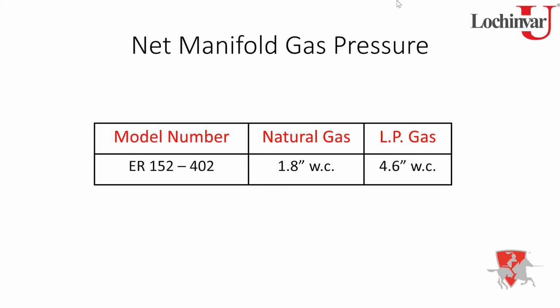So basically, at the end of the day, go out and buy a dual port manometer, then you don't have to deal with this. That's exactly right. Now, if for some reason we do need to adjust the setting of that regulator, because we know the air is fixed, we've got the air shutter set, we've got the air delivering what we want, but if our number's off, then we have to adjust the regulator.